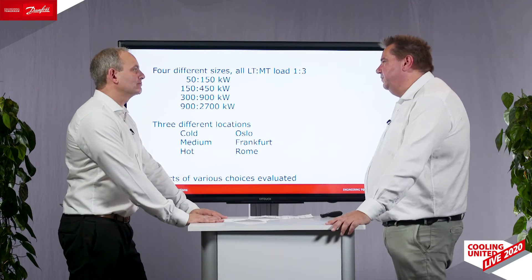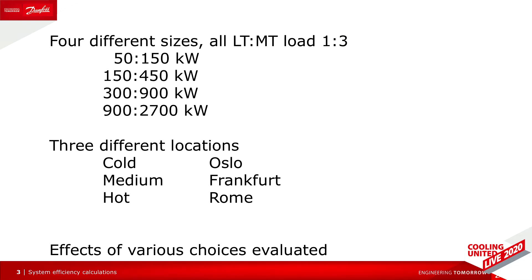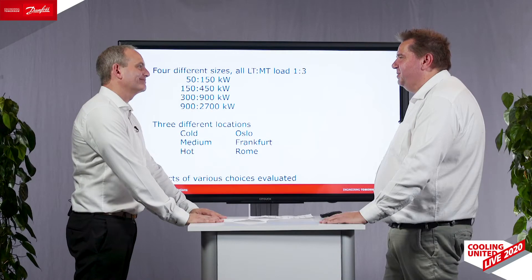But also an optimized version where we had basically all the bells and whistles that we could put into it to have the highest efficiency of the system. We also calculated in four different sizes, from relatively small — 50 kilowatts on the low temperature and 150 on the medium temperature — keeping that 3-to-1 ratio all the way up to the large system, which was 900 at low temperature and 2700 at medium temperature. We found no significant difference from the size of the system, so we skipped that in the last half.